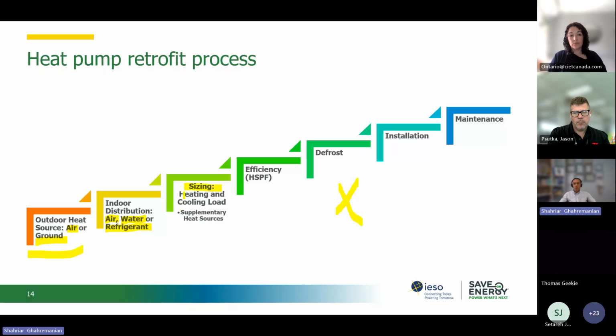Now it becomes the time for sizing the heating and cooling loads, actually. And then this is the time to see which type and size of heat pump is good for us. It depends on the price of the heat pump as well, actually. There are some cases where we need supplemental heat sources when we want to retrofit to heat pumps, because we're going to have a balance point. Basically, if this is the heat loss of a building, then the manufacturer will give you a graph that shows, based on the outdoor temperature, how much is the heat supply of the heat pump. So then this point is going to be the balance point, actually. And any extra heating that is required on the left-hand side of this X that you see here means that we need to provide a supplemental heat source, actually.